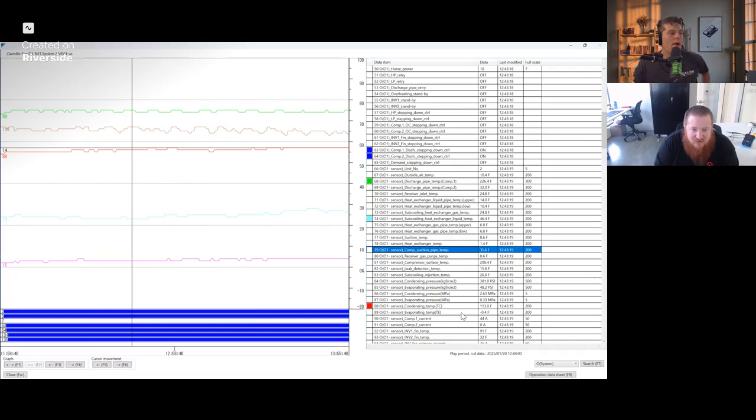What do we know about suction superheat, right? Negative 0.4 degrees is our actual TE, and our compressor is at 35. That's a 35-degree suction superheat. High discharge superheat, high suction superheat, but then you go, wait a minute, but you have high subcooling. And I go, is it though? Is it actually liquid? Because I'm pretty sure it might not be liquid.